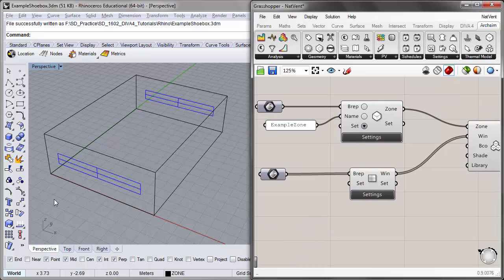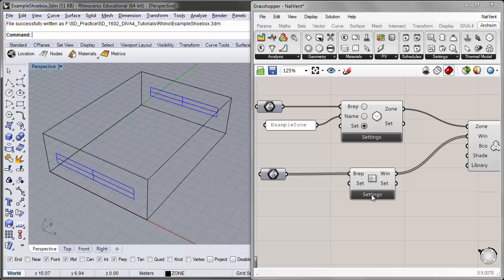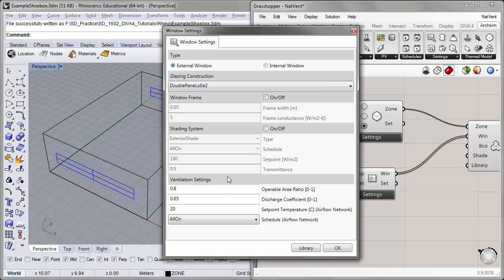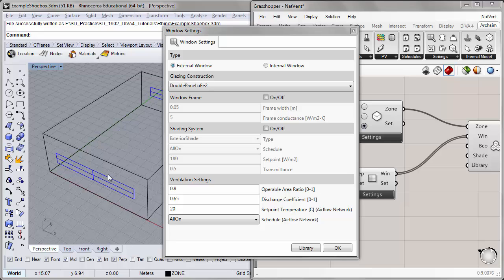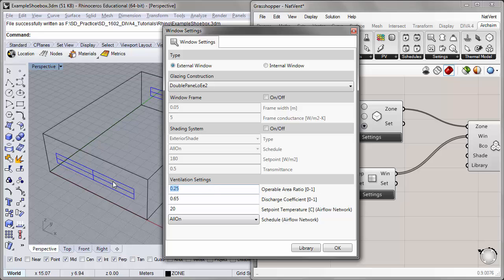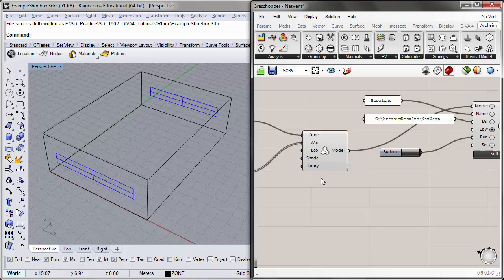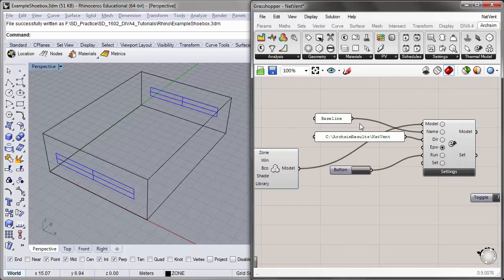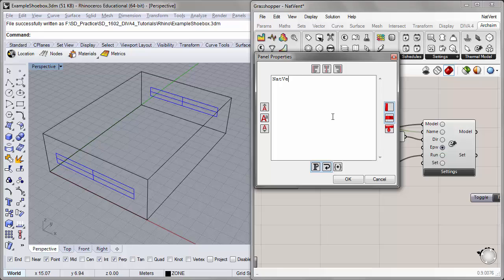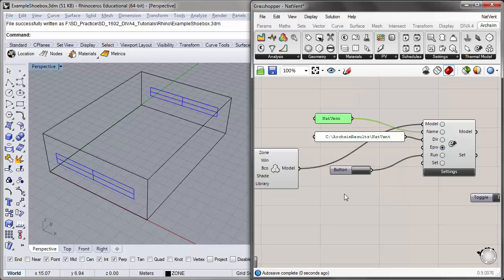We also have to associate windows to the natural ventilation settings. Under the window settings, there are some ventilation settings associated with these windows. The one we'll look at today is the operable area ratio — the effective open area that air can flow through in our window surface. I'll reduce this to 0.25 to be a little more conservative about the actual open area. I'll leave the discharge coefficient and the schedule the same. Now that we have this natural ventilation variant set up, I'll change the name from Baseline to NatVent.